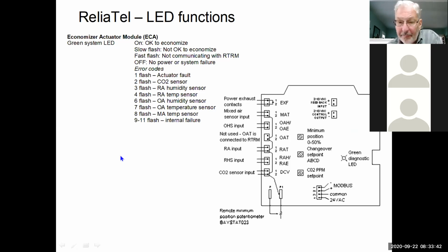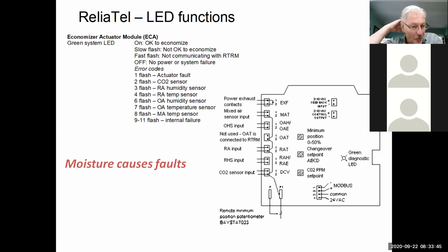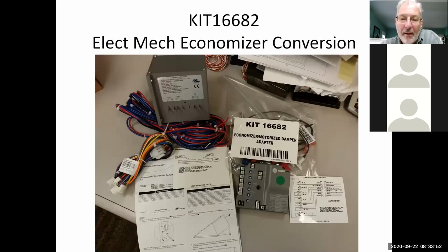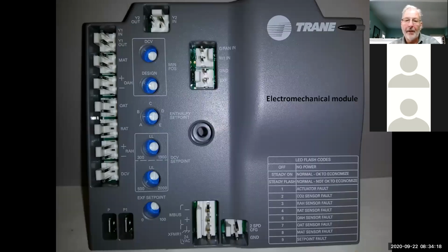So I don't need to go into a whole ton of detail. If you see moisture on controls, change them. There's probably an issue. Some of the old Honeywell electromechanical controls are replaced with kit 16682, and it's basically a rewire. If you run into these and have to change them, I've done a few. They're a little bit much the first time you do one, but give me a call if you have questions when you end up with these kits.